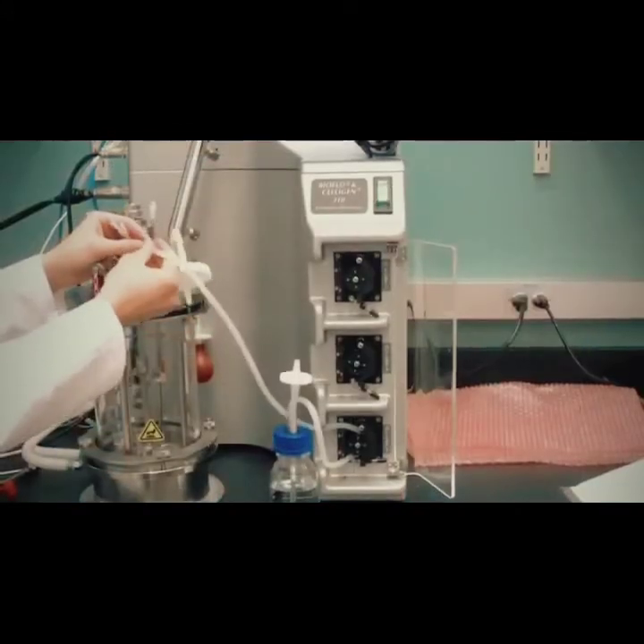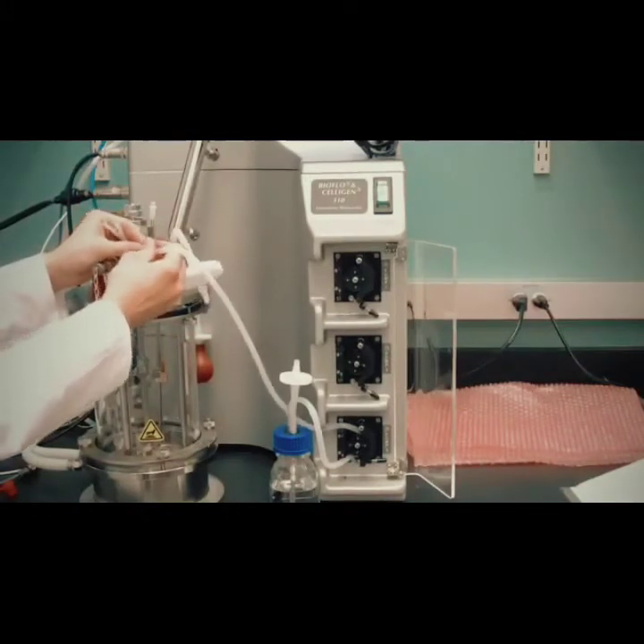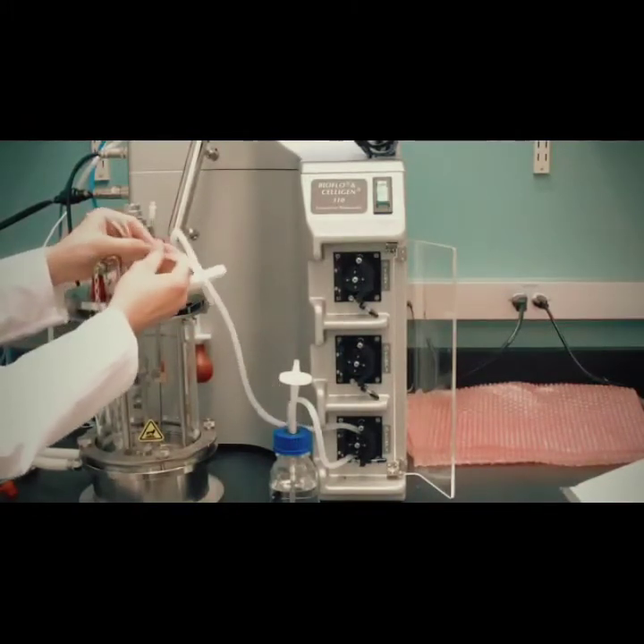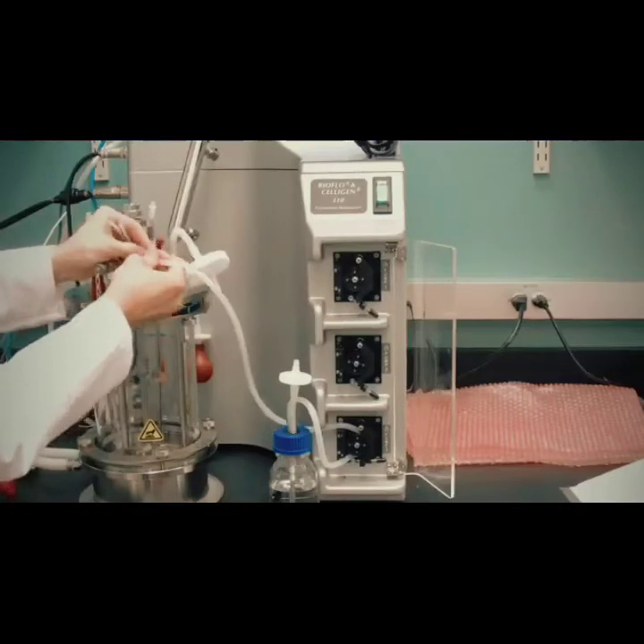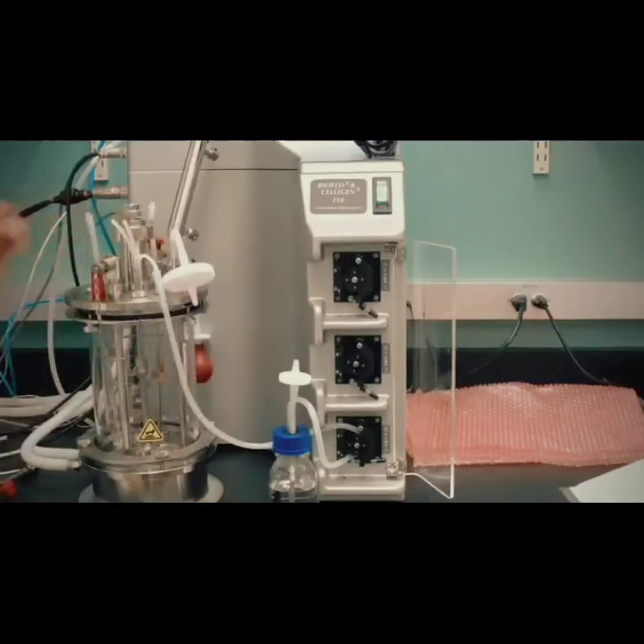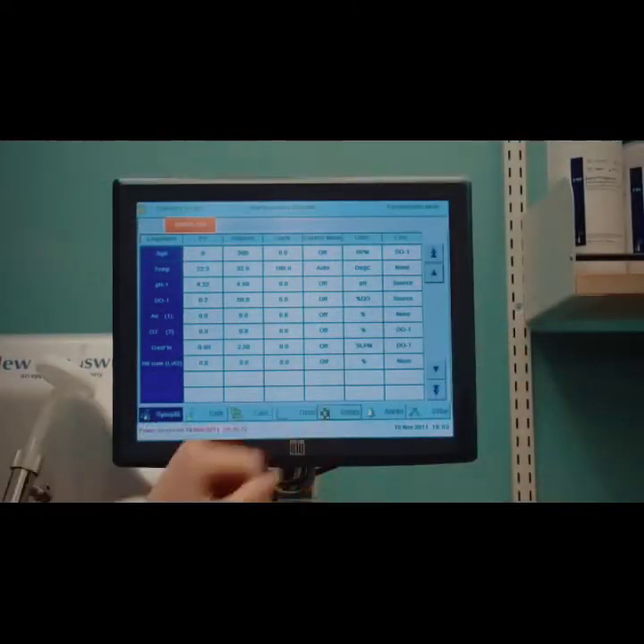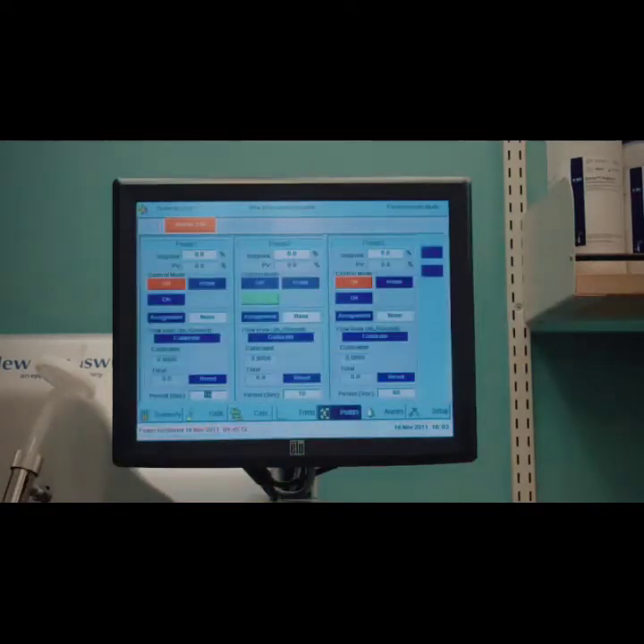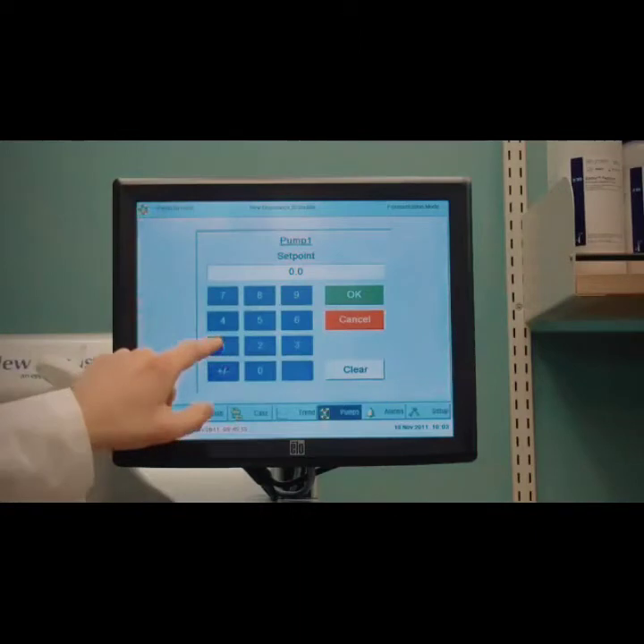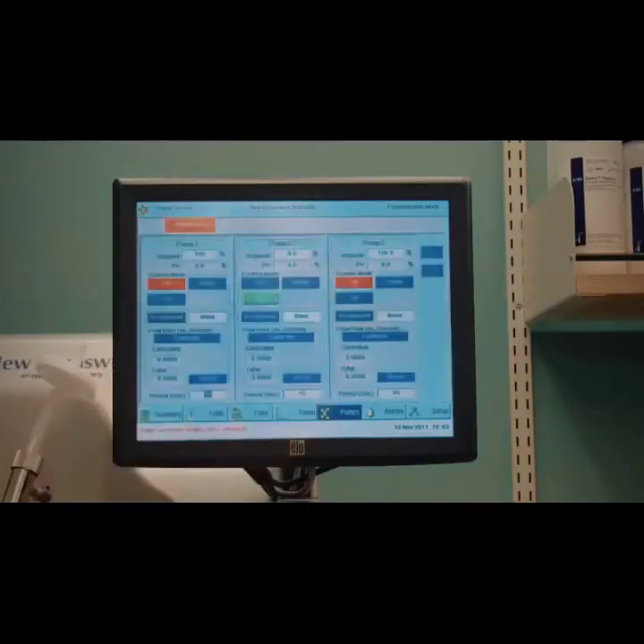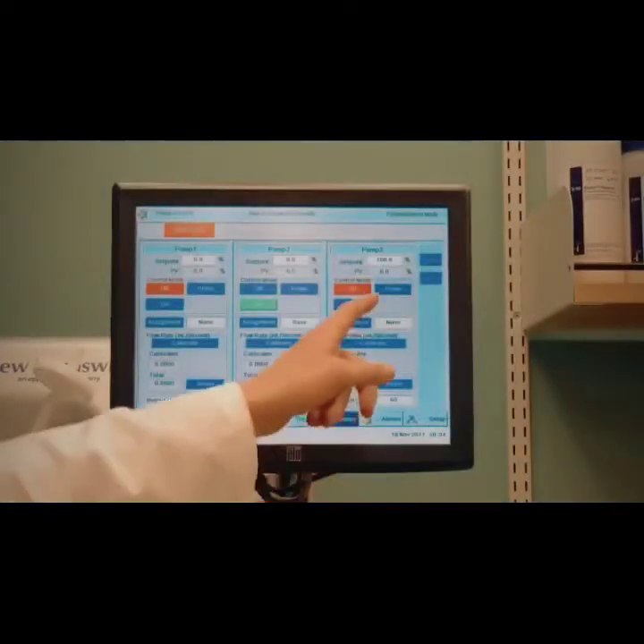Add glucose solution by threading the addition bottle tubing through the lowest peristaltic pump and connecting it to one tube on the addition triport. Remove the clamps. On the pump screen, change the pump power setting to 100 and press on until as much glucose solution as possible has been transferred into the fermenter. Reclamp the addition triport tubing before disconnecting the addition bottle.